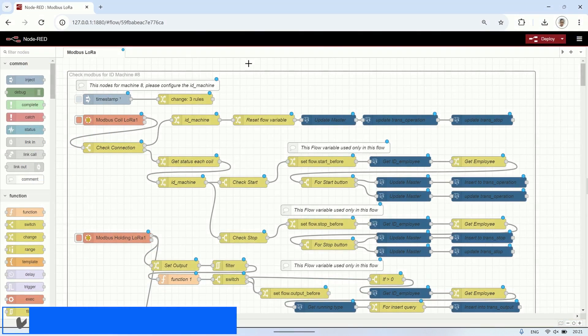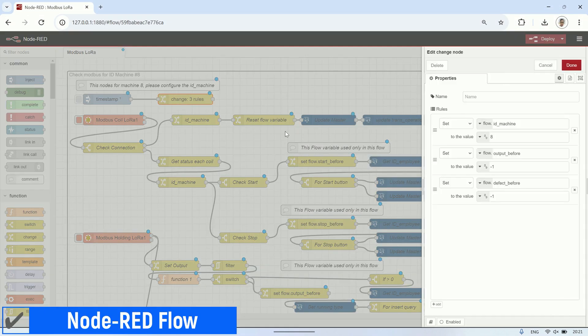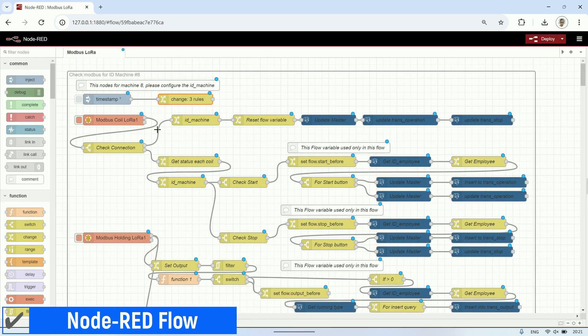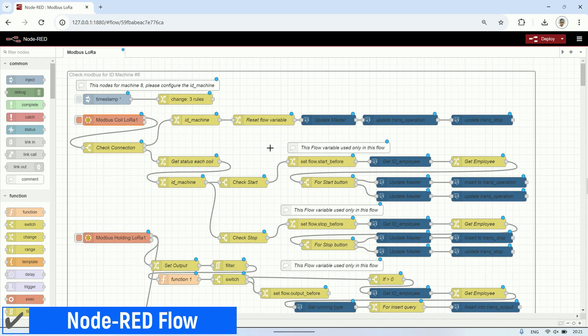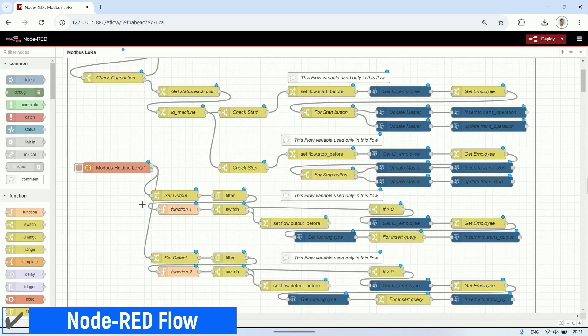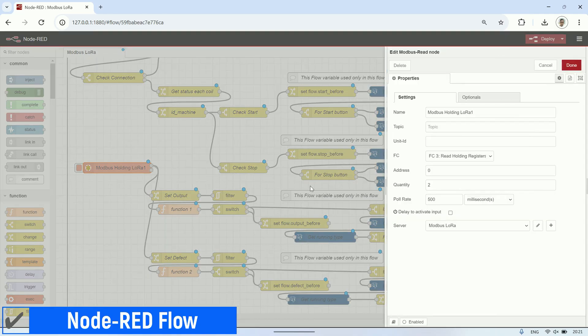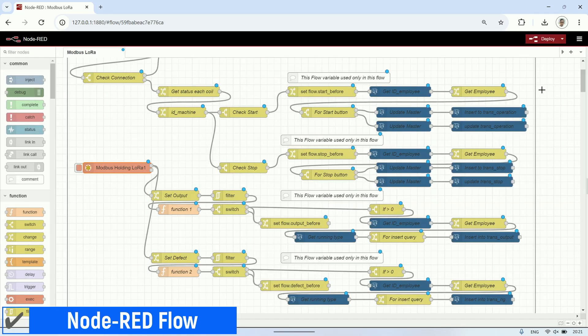Next, here is an example of the Node-RED flow I use. First, I create a variable for the machine ID, such as machine ID 8, which will be used for recording data. Then, I use the Modbus node to read the coil registers for the start and downtime status and record this data to the database. Additionally, I read the holding registers to store the output and defect counter values.